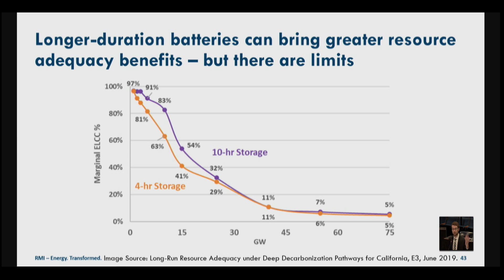This shows the marginal ELCC of 4-hour storage and 10-hour storage. This was from a study specifically for the California market. We can see that the ELCC of 4-hour storage declines more rapidly than that of 10-hour storage. 10-hour storage, because it's able to provide its full capacity over a longer period of time, is better suited for those longer peaks.